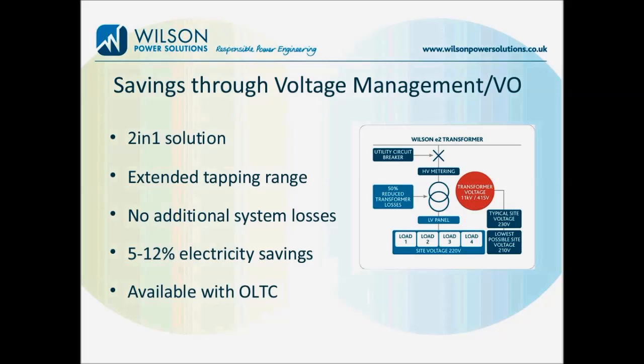In a nutshell, the transformer will be designed to deliver the required site voltage without any need for additional downstream equipment. So really you've got a two-in-one solution, and it minimises plant footprint, and so you avoid those additional system losses, including cabling from any other pieces of equipment. Now you can expect up to 12% saving on your energy bill by doing this.